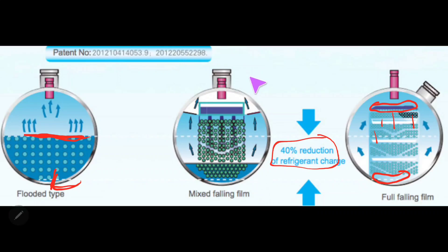The third type of heat exchanger, and actually these two are two that I actually see legitimately in the field, is a mixed falling film or a hybrid evaporator. A hybrid evaporator is exactly that. The goal is we're still using the concept of the falling film and having refrigerant rain down and just boil off as it goes and gets collected back into the suction. It has a distribution block up top. Liquid refrigerant is still injected into the top of it. It goes through a metering device outside of this distribution block. It's already in a saturated state by the time it gets put in up here, and then there's enough refrigerant left over that we can hit this bottom section here and actually have a little bit of standing liquid refrigerant in the bottom, just not near as much.